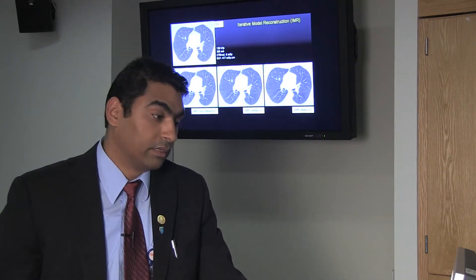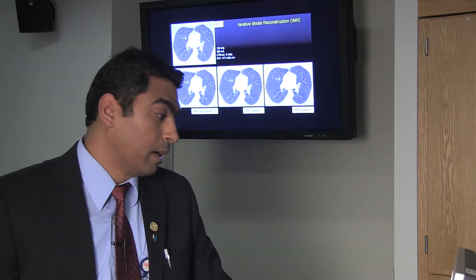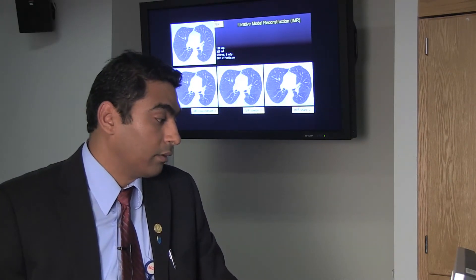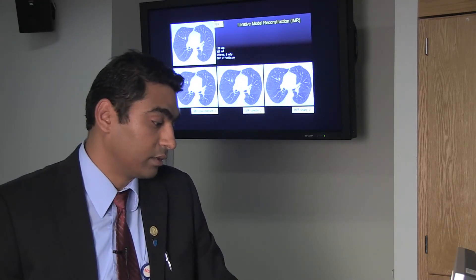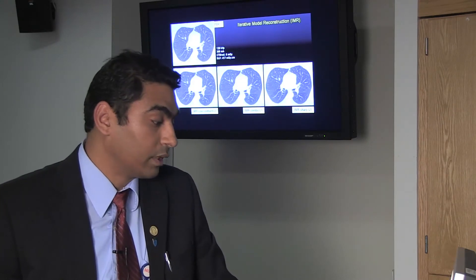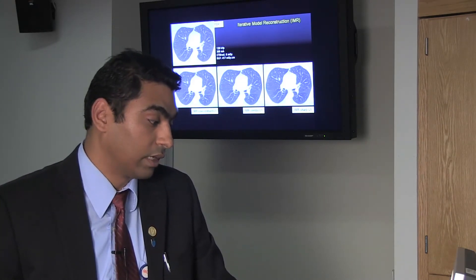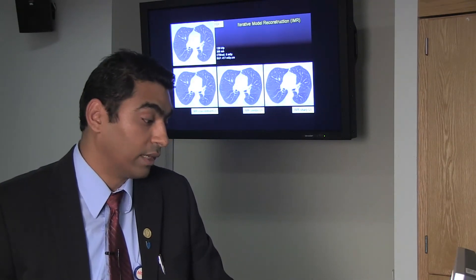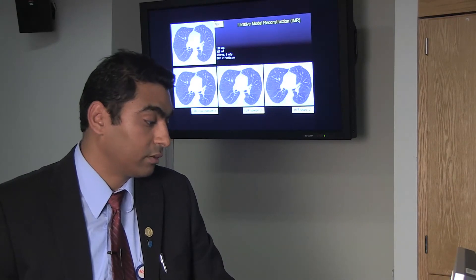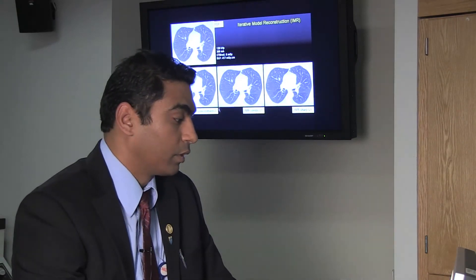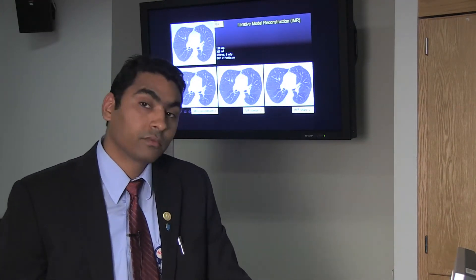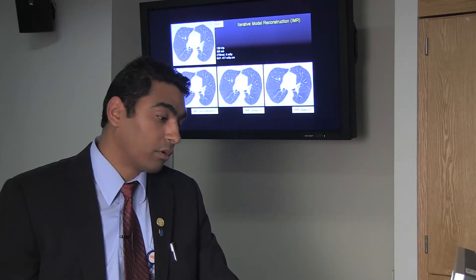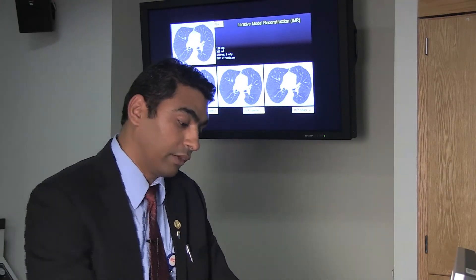Now let's look at Philips' iterative model reconstruction, commonly known as IMR. A patient was scanned at 120 kV, 300 mA, CTDIvol of 8 mGy, and reconstructed with filtered back projection. The same raw data was then reconstructed with different IMR settings: low contrast, combo, and sharp — each with noise reduction levels L1, L2, L3. Looking at the posterior lung parenchyma where streaks come from the vertebral body, with low contrast settings the streaks remain, with combo they almost disappear, and with sharp setting they are completely gone. So it's very important to select the right algorithm setting to achieve the desired image quality.